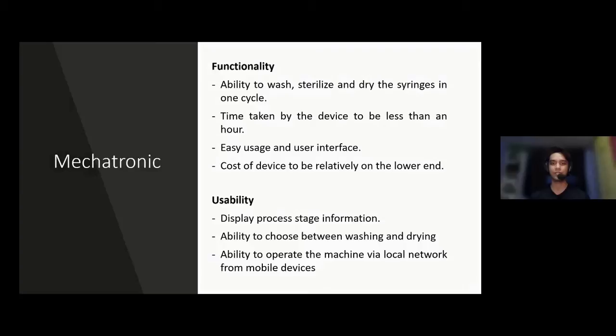Under functionality, there are three stages that have to be done in one cycle fully automated, and these are washing, sterilizing, and drying. There's also the requirement for one cycle to be completed in less than an hour, and also for the cost of the device to be relatively low. Under usability, the nurse has the display of the process stage information, the ability to choose between washing and drying, and also the ability to operate the machine via local network from any mobile device.